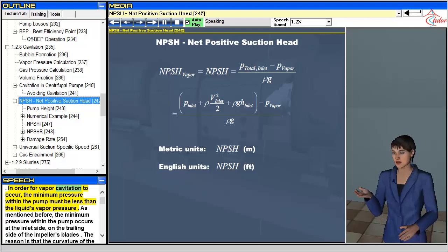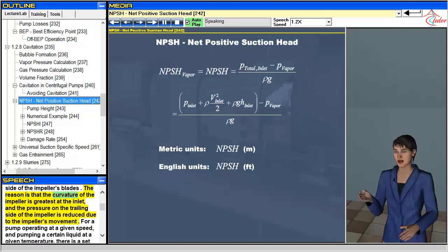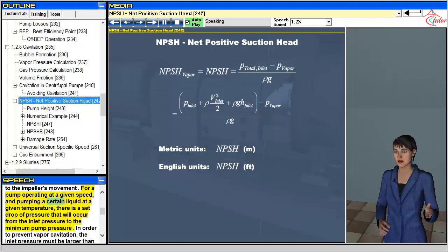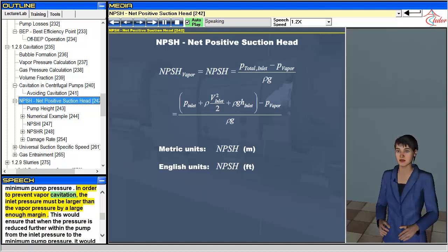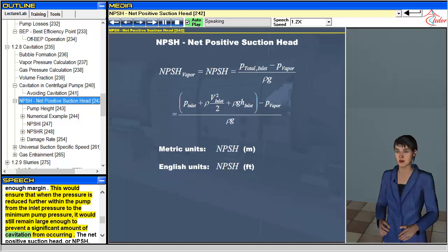In order for vapor cavitation to occur, the minimum pressure within the pump must be less than the liquid's vapor pressure. The minimum pressure within the pump occurs at the inlet side on the trailing side of the impeller's blades, because the curvature of the impeller is greatest at the inlet and the pressure on the trailing side is reduced due to the impeller's movement. For a pump operating at a given speed and pumping a certain liquid at a given temperature, there is a set drop of pressure that will occur from the inlet pressure to the minimum pump pressure. In order to prevent vapor cavitation, the inlet pressure must be larger than the vapor pressure by a large enough margin, ensuring that the pressure still remains large enough to prevent significant cavitation from occurring.